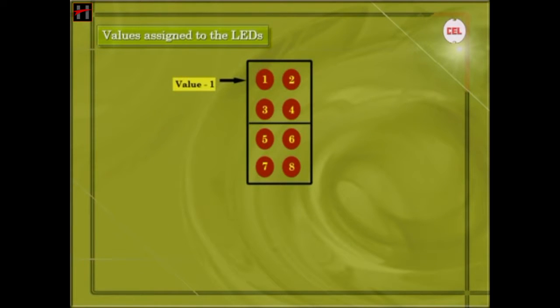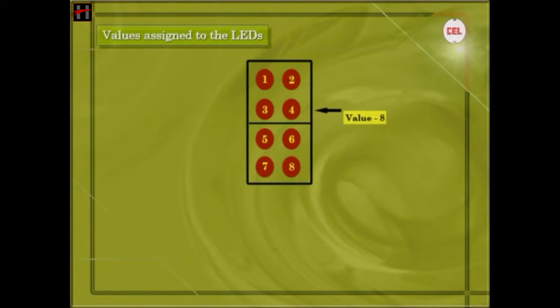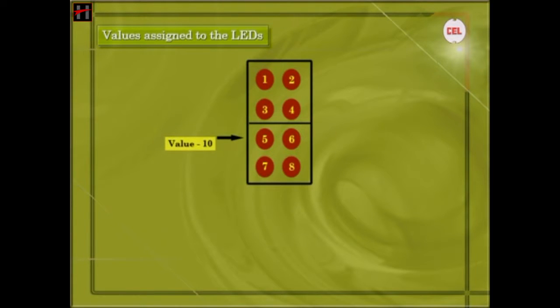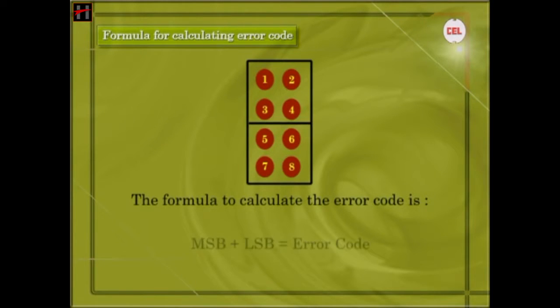LED 1 has a value of 1, LED 2 has a value of 2, LED 3 has a value of 4, LED 4 has a value of 8, LED 5 has a value of 10, LED 6 has a value of 20, LED 7 has a value of 40, and LED 8 has a value of 80. The formula to calculate the error code is MSB plus LSB, which gives the error code.